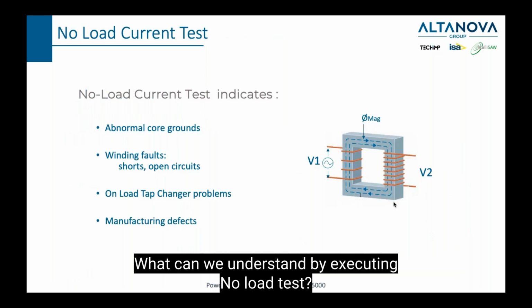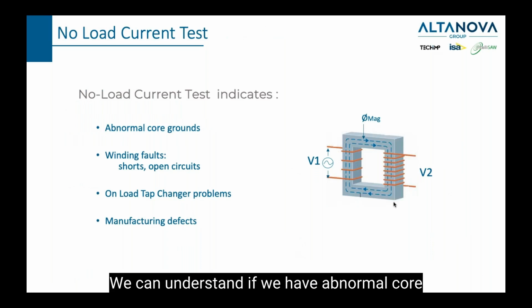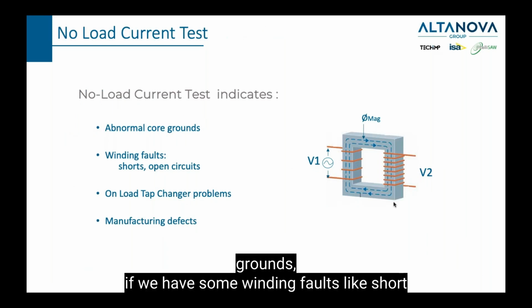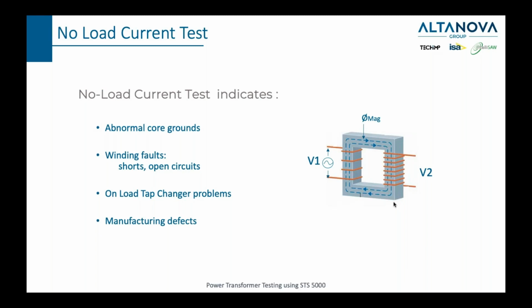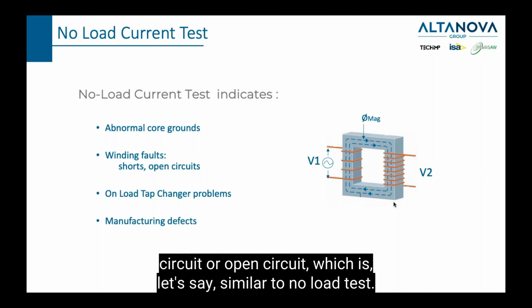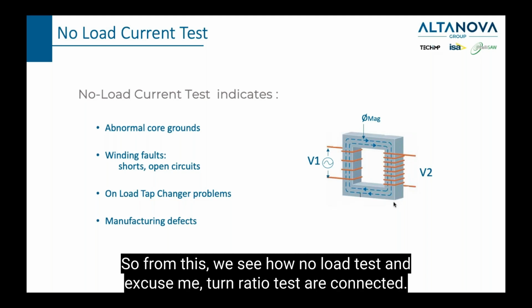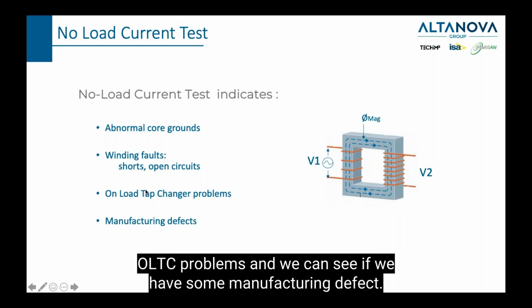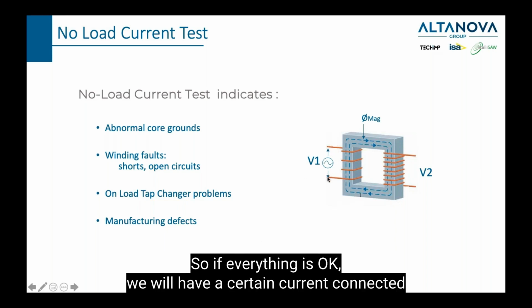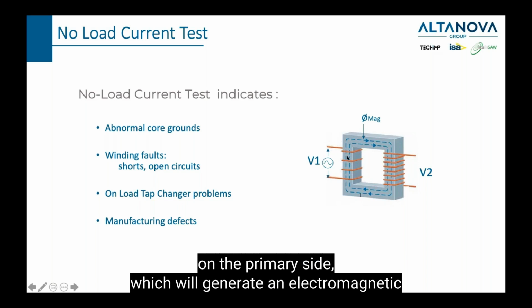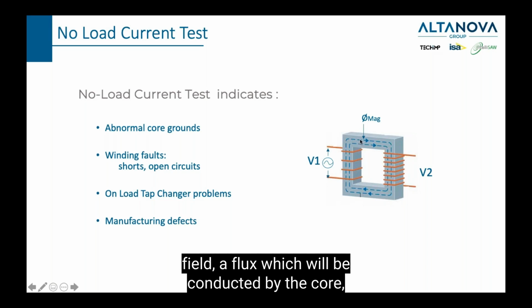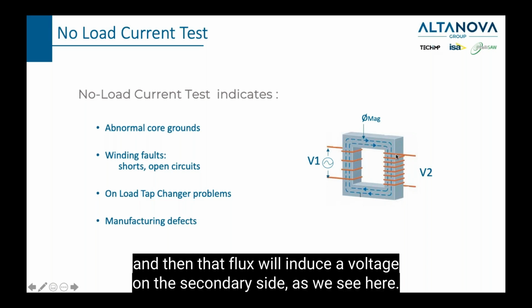What can we understand by executing the no load test? We can understand if we have abnormal core grounds, or some winding faults like short circuit or open circuit, which is, let's say, similar to the turn ratio test. So from this we see how the no load test and turn ratio test are connected. We can see if we have some OLTC problems, and we can see if we have some manufacturing defects. So if everything is okay, we will have a certain current connected on the primary side, which will generate an electromagnetic field, a flux which will be conducted by the core, and then that flux will induce a voltage on the secondary side, as we see here.